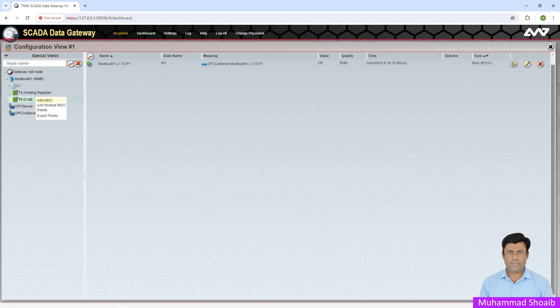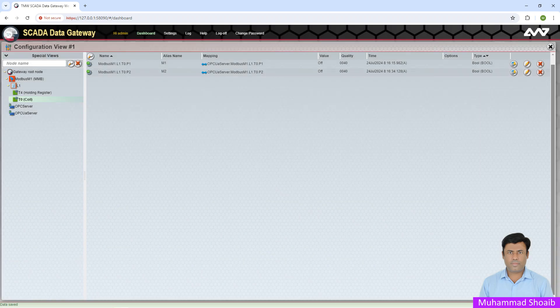Add one more tag — write M2 — and press OK. Now the SCADA Data Gateway Modbus master configuration is completed. Now we'll run our Modbus slave device or Modbus server application. For your case it might be actual hardware, but for my case I'm using a simulator — the ModSim simulator — as a Modbus TCP slave or server.